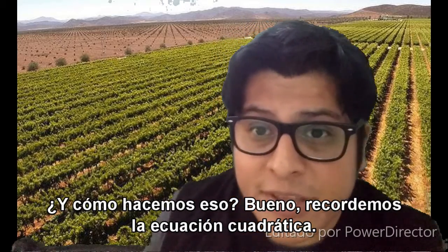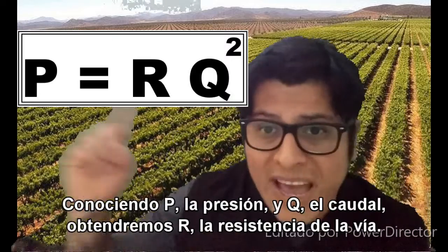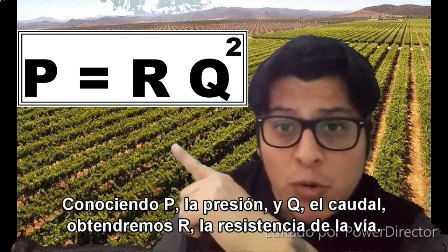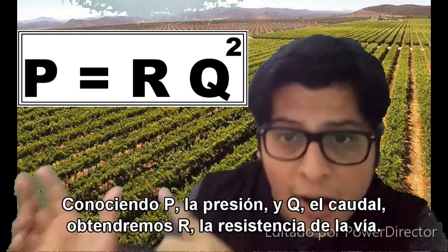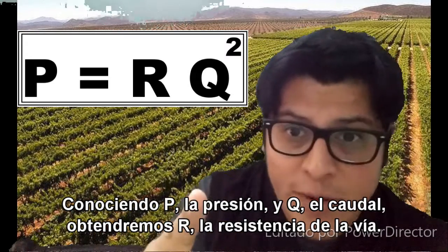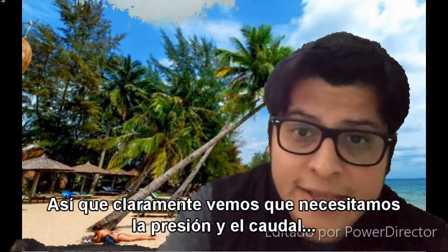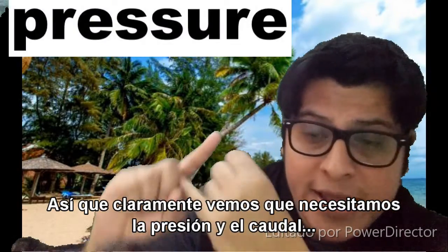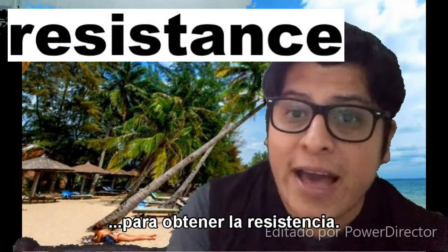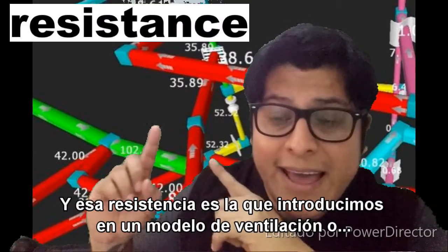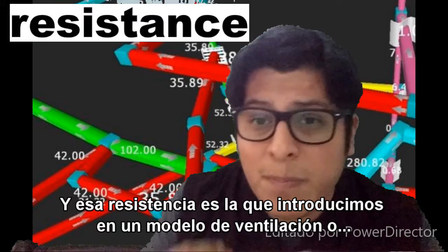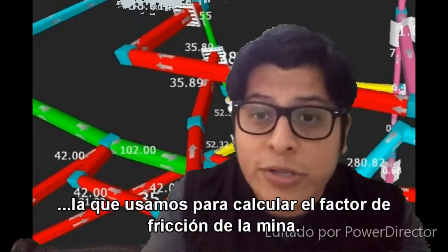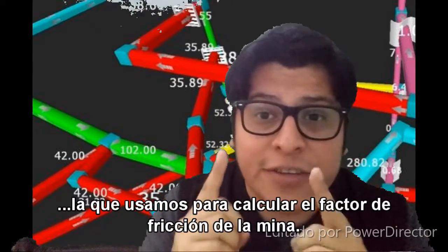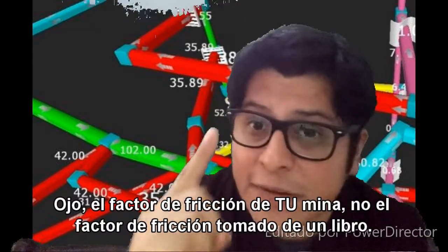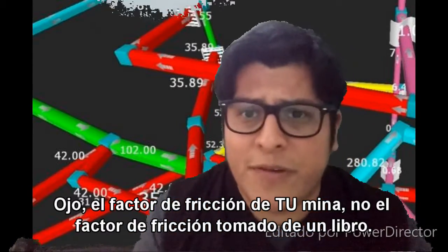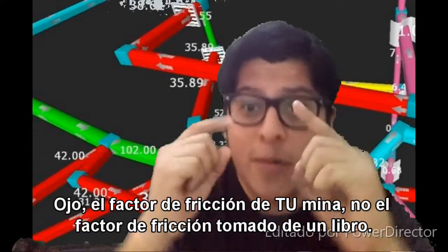Well, let's remember the square law right here. If we have P, the pressure, Q, the airflow, we will know R, the resistance of the airway. So we clearly see that we need both pressure and airflow in order to have the resistance. And this is the same resistance we plug into a ventilation model or use to calculate a site friction factor. A site friction factor, not some book friction factor, the friction factor from your mine.